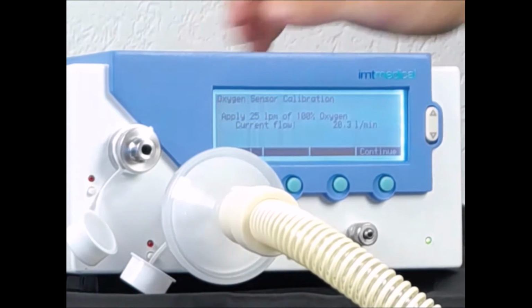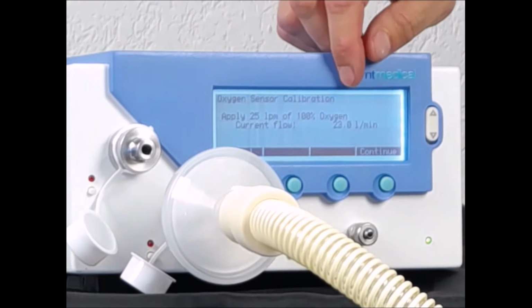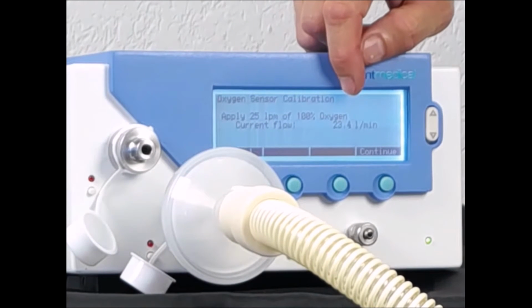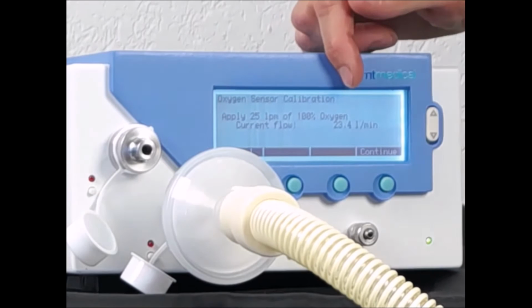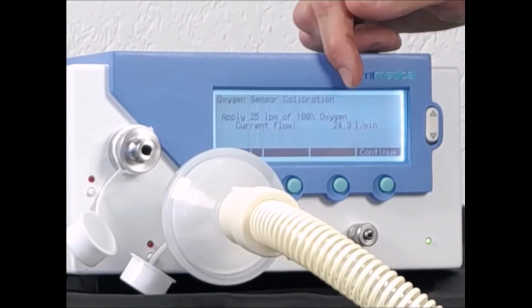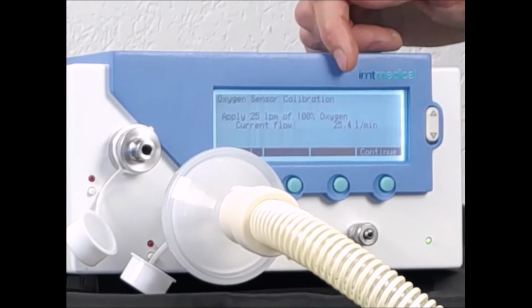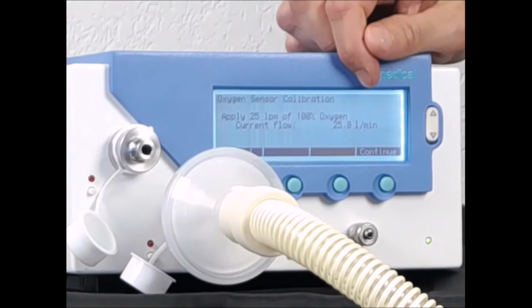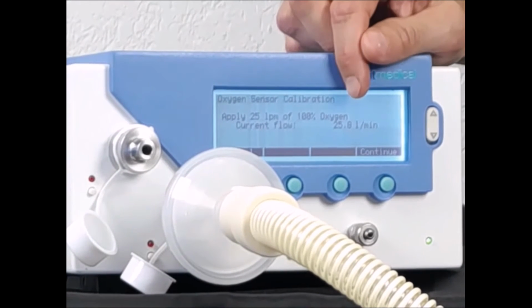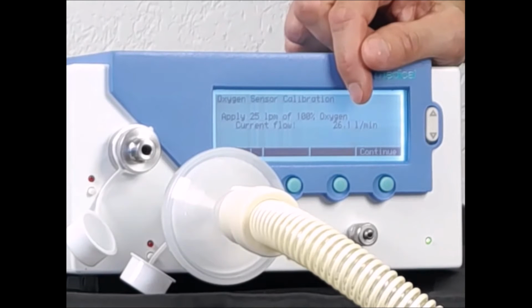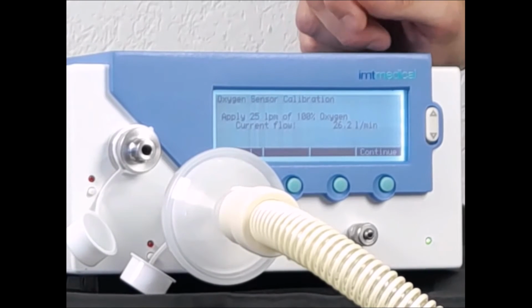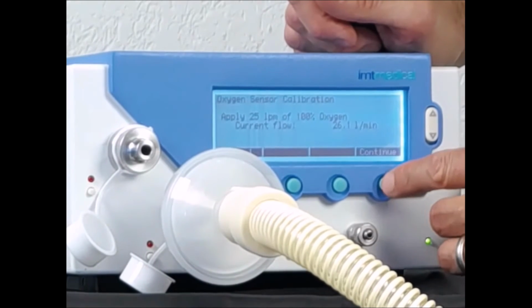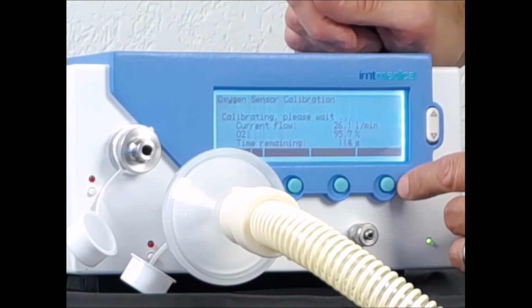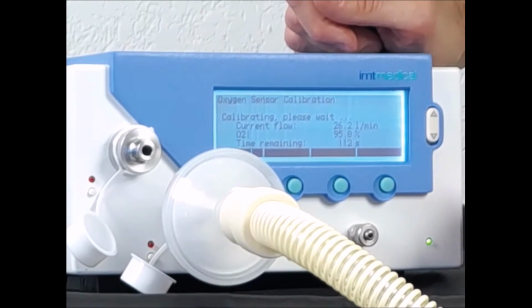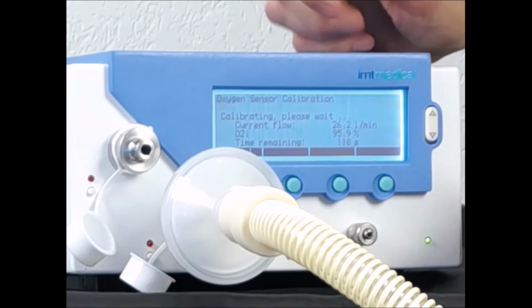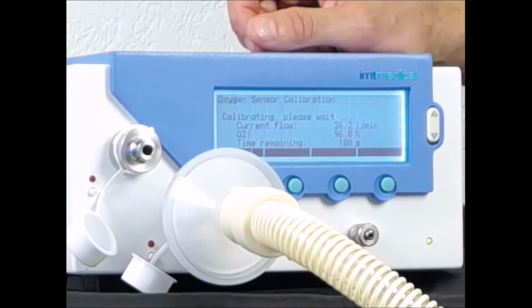Here on the right side, we see the actual flow. It is now 23. That will be enough, but I can still fine-tune that a little bit to get up to 25. So the flow here is not important, but it is important that the oxygen cell receives enough fresh oxygen. And then I press continue, and it is taking 2 minutes until the 100% oxygen point is calibrated.